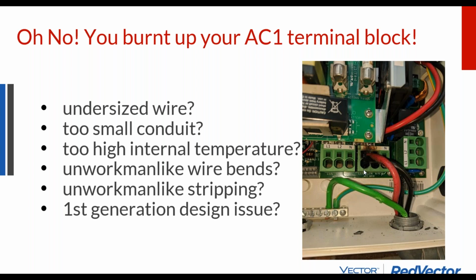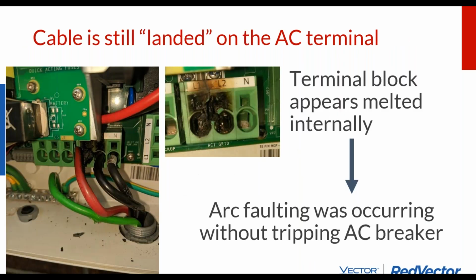So what caused this to happen? What we see is this is an arc fault, because the neutral's the ground connection, and what we've got is some arcing between leg 1 and leg 2 here, and so that is not a ground fault contained somewhere else in the system that might be connecting to ground and pulling electricity from power into the neutral along with it, or something like that. These two wires plugged into this terminal block touched, and that was causing arcing between them, and it burned up that terminal block. And so the question is, well, why wouldn't that trip the breaker?